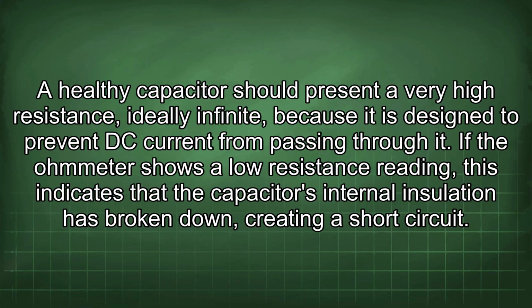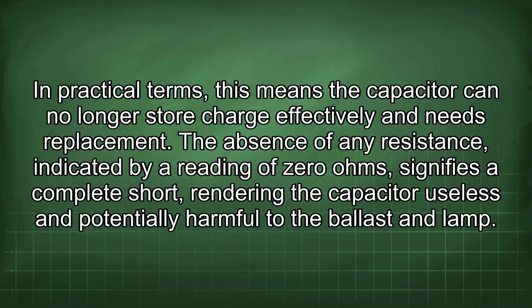If the ohmmeter shows a low resistance reading, this indicates that the capacitor's internal insulation has broken down, creating a short circuit. In practical terms, this means the capacitor can no longer store charge effectively and needs replacement. The absence of any resistance, indicated by a reading of 0 ohms, signifies a complete short, rendering the capacitor useless and potentially harmful to the ballast and lamp.